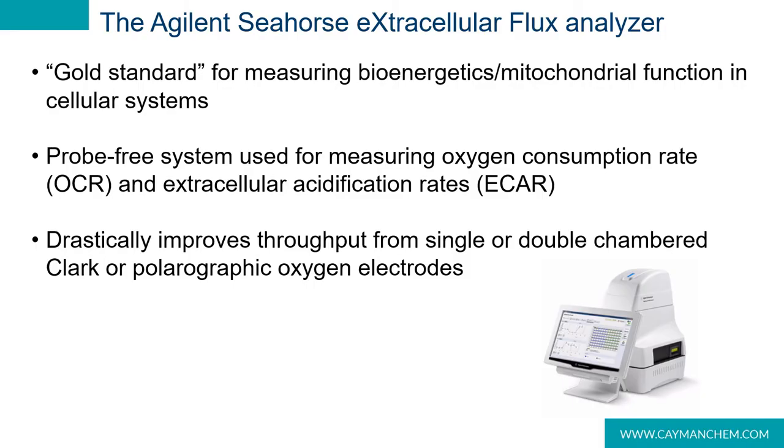The Seahorse XF, or extracellular flux analyzer, is an incredibly important and powerful tool used for measuring cellular bioenergetics. Before the invention of XF technology, researchers used a Clark-type or polarographic oxygen electrode, which while extremely accurate were incredibly low throughput, using a single or in some cases a double measurement chamber. The XF analyzer uses specialized plastics embedded with oxygen and pH sensitive probes to accurately measure oxygen concentration and extracellular pH in a 24 or 96 well format.